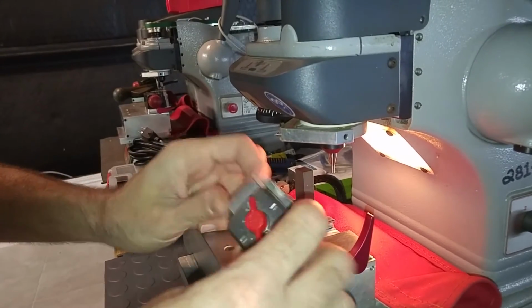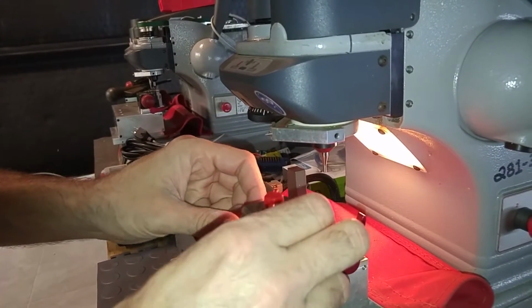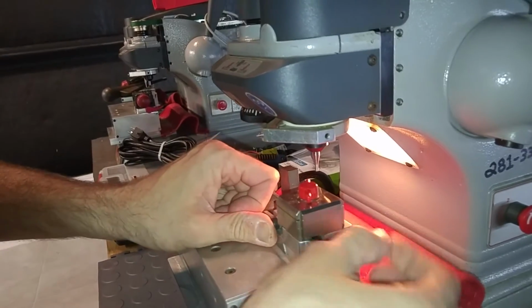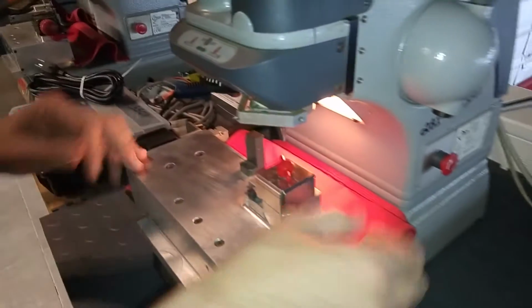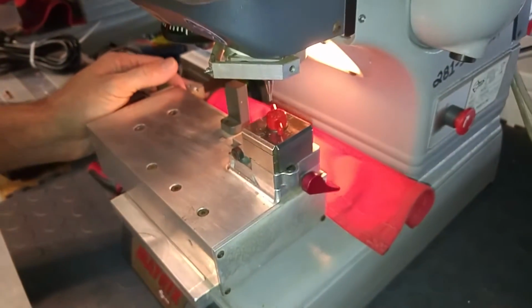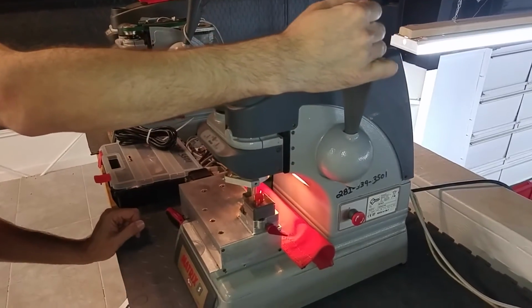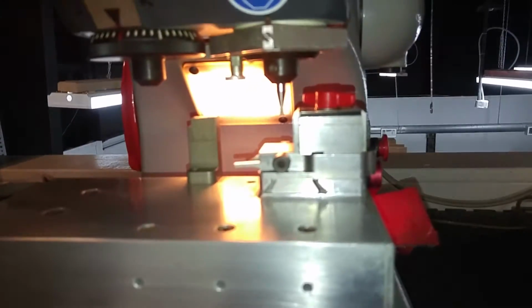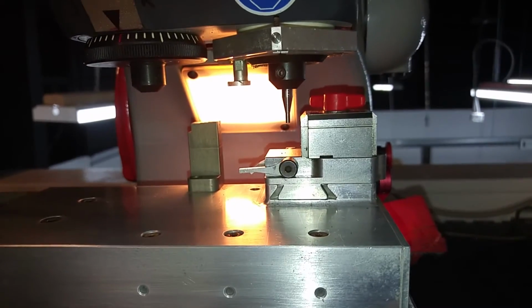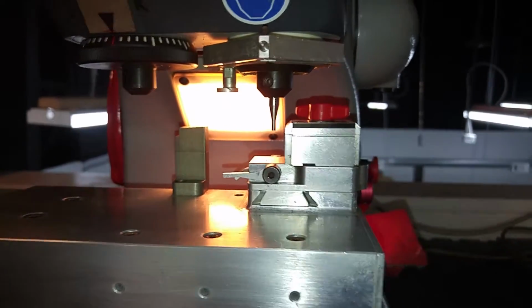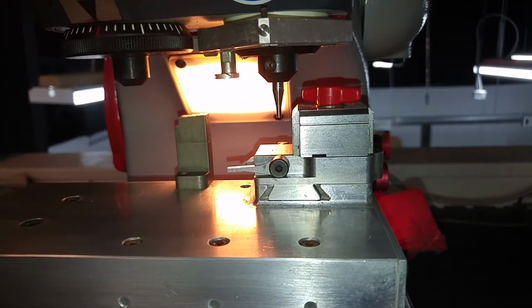We'll place jaw number 2 on the deck with A facing inwards towards the machine, all the way in, and we'll tighten it down. I'll come over here to the machine and say calibrate cutter. Hit 2 for jaw number 2, and then enter. The machine will go into position, and then direct you on the computer to please lower the cutter and start again. So we'll lower our stylus down to where we're on our flat surface of the side of the jaw, not the bevel, and tighten our handle and then say continue on the computer.